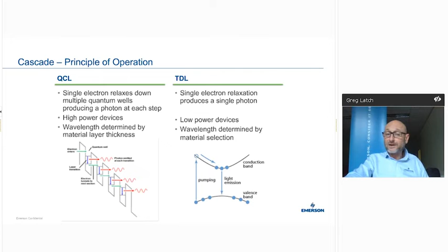This gives you a quick overview of the size. On the left there's a QCL unit. Something I didn't comment on, one of the reasons why you also get a wavelength change in those multiple photon releases is because laser technology can be high powered. We actually use a high powered style of laser which has an embedded Peltier cooler. So based on a heat cool cycle you do get a slight frequency shift, versus TDL, which is more of a lower power style of technology.